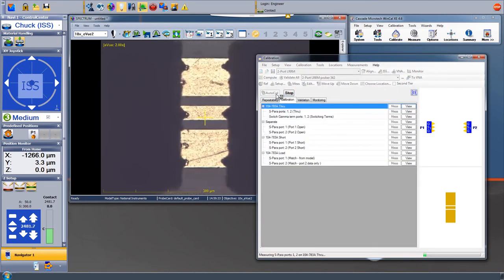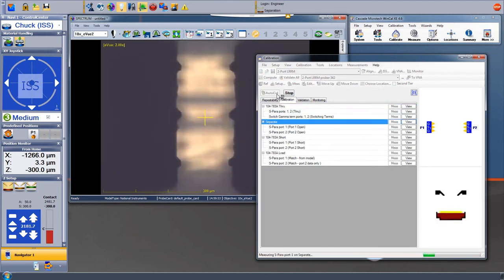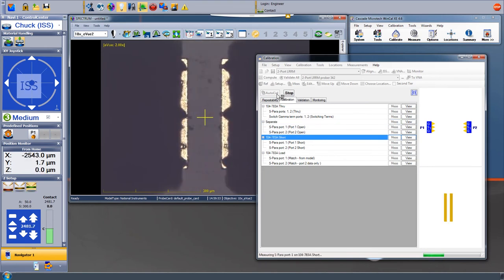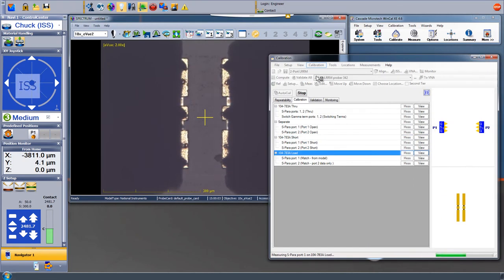The probe station immediately sends us to the Through standard. Then we measure the Open standard, which is where the probes separate from the substrate. Next, we measure the Short standard. And last, we measure the Load standard.